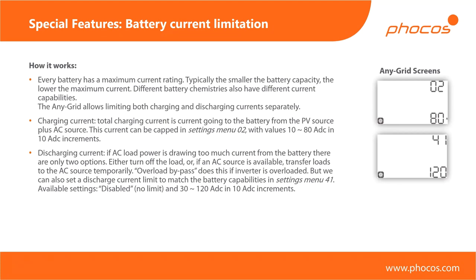Too much charging current causes overheating in lead-acid batteries. For lithium batteries, the battery management system will notice too much current and simply shut down, or the battery could even be damaged if not well protected. This is an important setting when using small batteries — you can limit the charging current going into the battery.